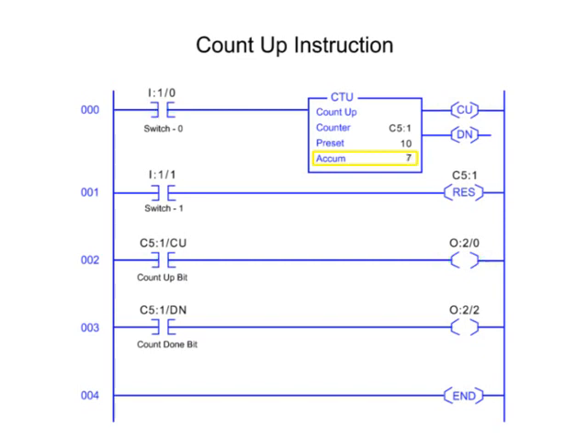After the accumulated value reaches the preset value, the counter instruction done control bit is enabled. The accumulated count is retained until cleared by the reset instruction addressed same as the counter file.